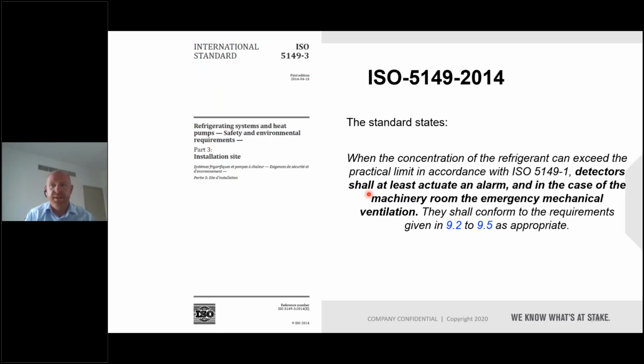Then we have the international standard, ISO 5149, which is based on one of the European standards, EN 378. It sets concentration limits for the gases in the document. If there is a risk that the concentration could increase above the limit, then a refrigerant alarm is needed to alert inside and outside the room and to activate the mechanical ventilation system. So most of these guidelines want a ventilation system. You have to alert responsible personnel, alert inside the room, and then activate a mechanical ventilation system to remove the dangerous gas from the room.